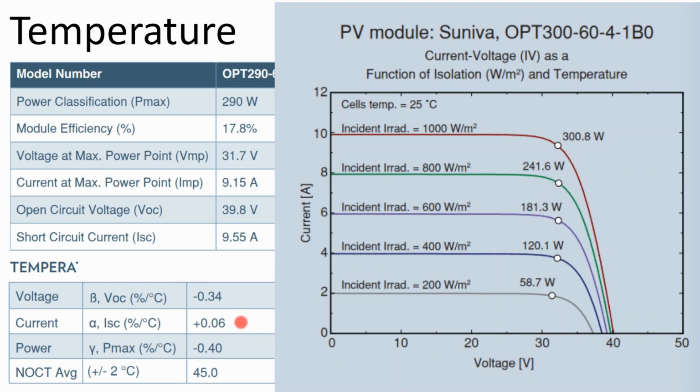So if on a hot summer day you get a breaker that trips, you're in luck. It's probably that the breaker, which has overcurrent protection, has tripped because it was undersized, and your system meets its maximum current capacity at high noon, on a full power day, slightly high. Voltage, on the other hand...